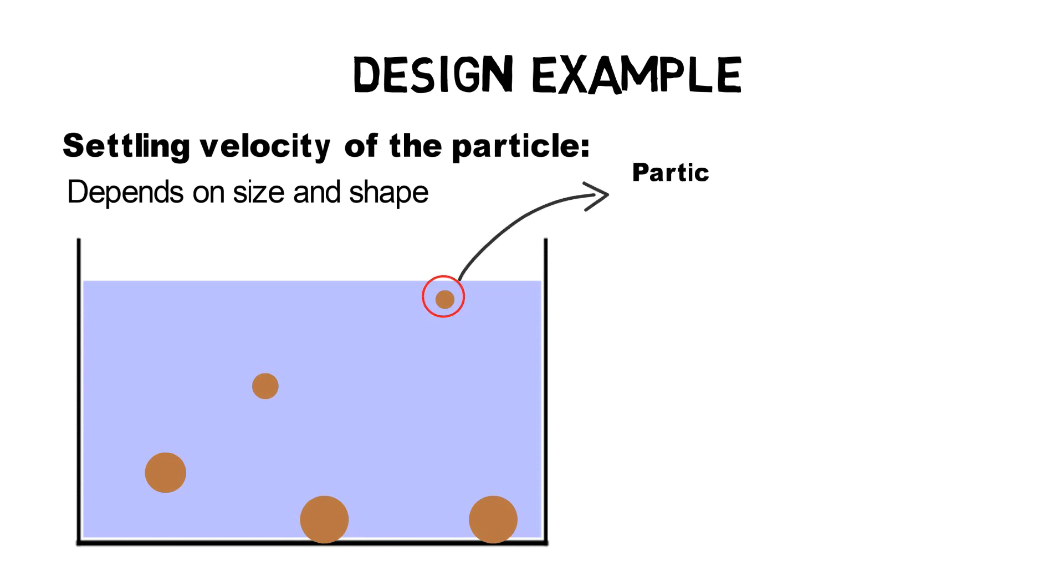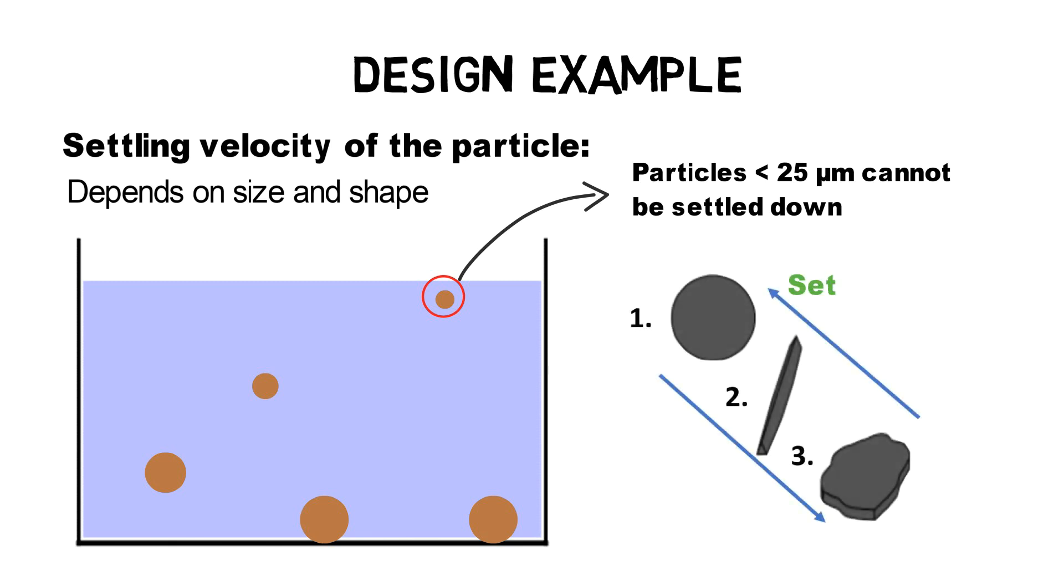Particles which are smaller than 25 micrometers can usually not be settled down at all because drag forces, turbulences, rising particles and others within the sedimentation basin are bigger than the particle settling force. Also, spherical shaped particles settle better than flat shaped particles as their form offers less contact area for drag forces.